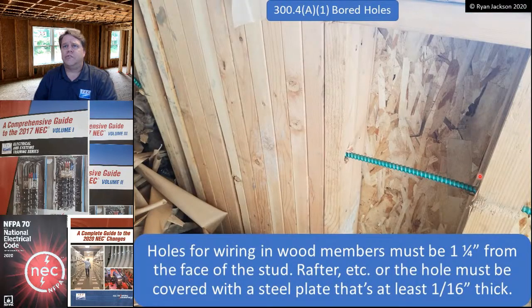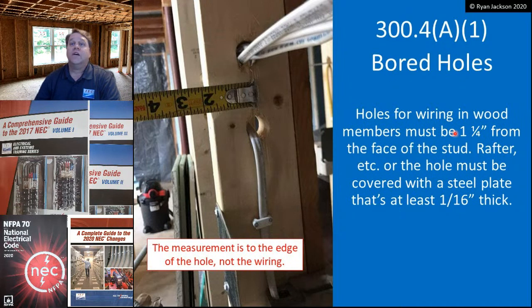So, bored holes, 300.4(A)(1), we're talking about wood. Holes for wiring in wood members must be 1 1/4 inches from the face of the stud or rafter, etc., or the hole must be covered with a steel plate that's at least a 16th inch thick. So, drill it in the middle of the stud, and that's all you've got to worry about. Now, I want to point out, somebody sent me this photograph and they were upset. They said, oh man, this stupid inspector is making me put nail plates. Look at this. It's 1 3/4 inches from the hole. You don't measure from the middle of the hole. You measure from the edge of the hole. So the inspector was absolutely correct. So you measure from the edge of the hole for this 1 1/4 rule.